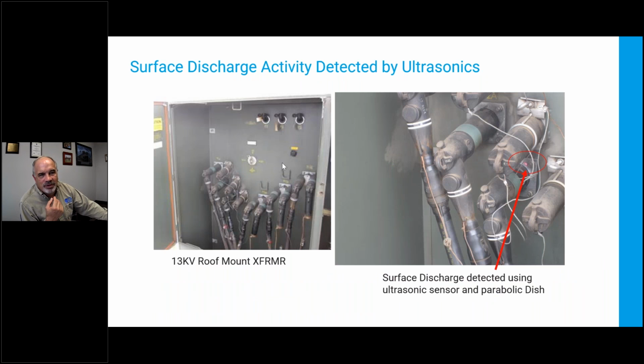Here's an example of surface PD detected with ultrasonic. Here's where we had found some ultrasonic signature with the door closed from the gap that said this could be PD. Went back, stood back, and ran the parabolic dish. It has a laser sight in it. Ran it up and down all the different terminations until we found the highest level of energy. And if you look right here, you can see the red dot from the laser sight, and right next to it is that white powder. It's very characteristic of PD. None of the other bushings have any white powder residue.